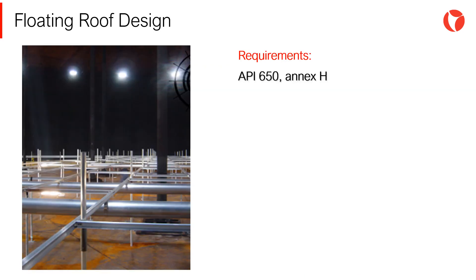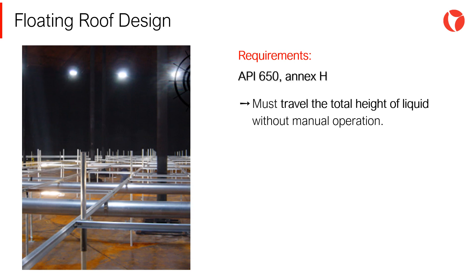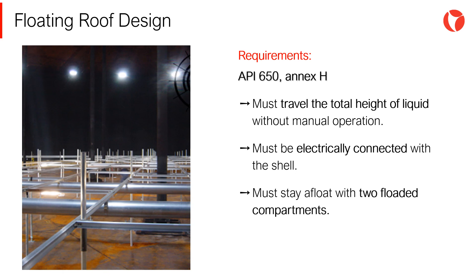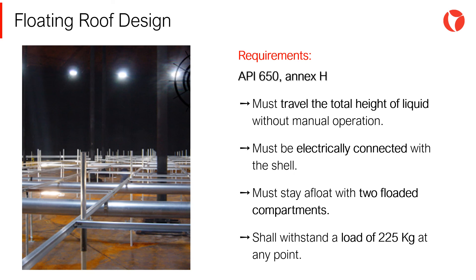The design of internal floating roofs must comply with the requirements of Annex H of the API 650 code. Some of the main requirements are: the roof must travel the total height of the liquid without manual operation; it must be electrically connected with the shell; the roof must stay afloat with two flooded compartments; and the roof shall withstand a load of 225 kg at any point.